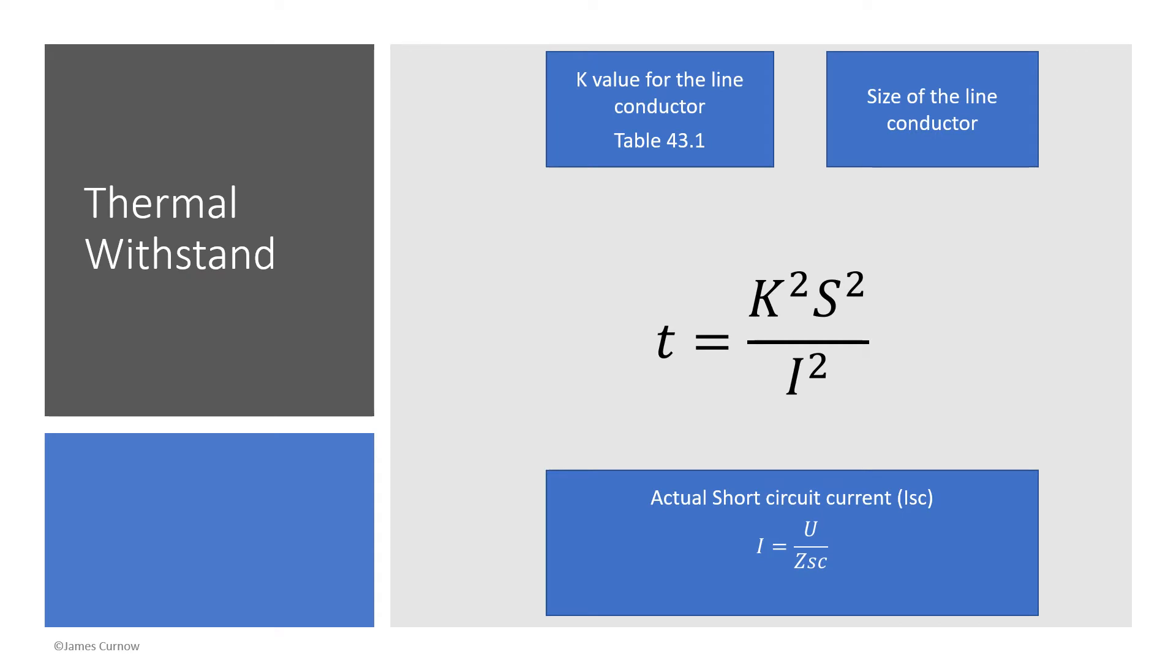Looking at the first equation in more detail, the equation for thermal withstand, what we're looking for here is the time in seconds, the time that the cable can withstand that level of short circuit current. The formula is T equals K squared multiplied by S squared divided by I squared. The K is the K value for the line conductor which is found in table 43.1.